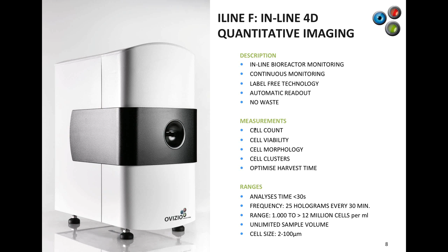The current range is from 1,000 to 12 million cells per milliliter, and we are working on increasing this cell density to more than 100 million cells per milliliter. The cell size that we typically measure with this microscope is from 2 to 100 micrometers, but that can be adapted depending on the needs. The system also comes with this disposable, which we call the BioConnect. The disposable is tubing with a new pump that we have developed. It's a membrane pump that is like a heart, with an inlet and an outlet. The throughput is 4.8 milliliters per minute, and the cells stay a maximum of 2 minutes within the fluidics.